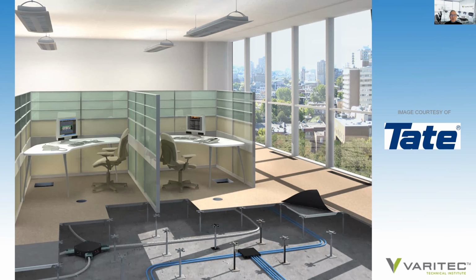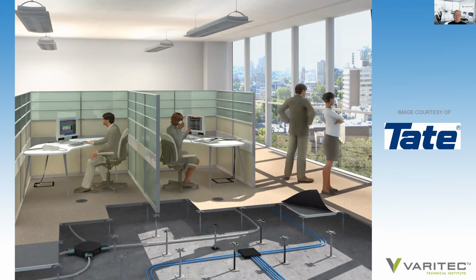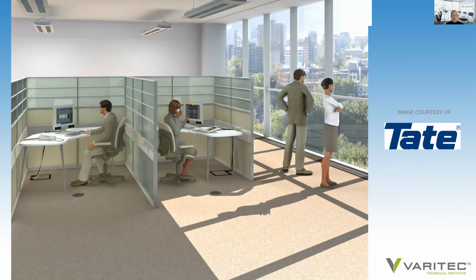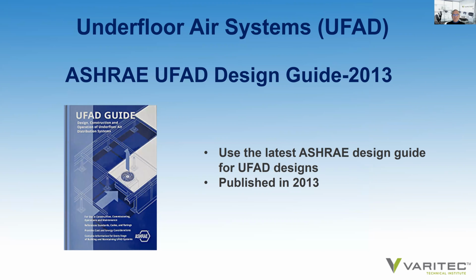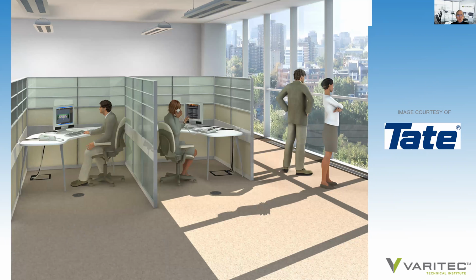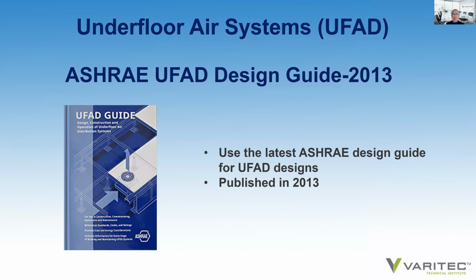Then furniture goes into place, and then the devices, the building is commissioned, and you have occupants, and this is how the floor actually looks upon completion. As you can see, the diffusers are located at each occupant in their cubicles, and this again conforms to ASHRAE's Epidemic Task Force guidelines for personalized ventilation at each occupant. So you have that advantage with the UFAD system.